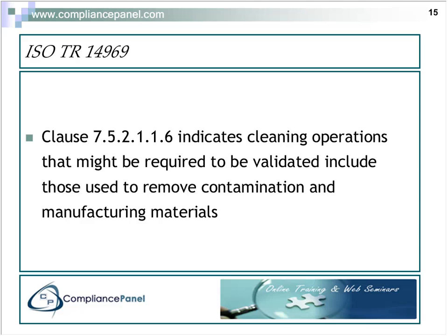Now, the numbering of this does follow the numbering of 13485. In fact, this document does include the entire text of 13485 in this document. So if you had your choice of which one to buy, I would buy 14969 and not buy 13485, because all of the requirements from 13485 are located inside 14969, right adjacent to the discussion of each of those requirements.